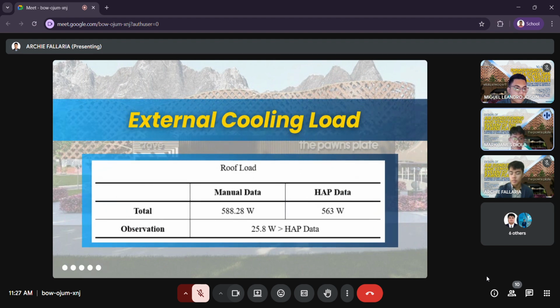So the next table shows the total roof load and its comparison to the HAP data. In the manual calculation, the total heat gain through the roof is 588.28 watts. This load is primarily due to the solar radiation absorbed by the roof surface and conducted into the interior area, especially significant in a tropical climate with high solar exposure. According to HAP software, the roof load is slightly lower at 563 watts, with a difference of 25.8 watts between the two calculations. This variation is well within acceptable limits, confirming that the roof insulation and the construction materials are effective in reducing the solar heat gain, and the HVAC system is appropriately sized to handle it.